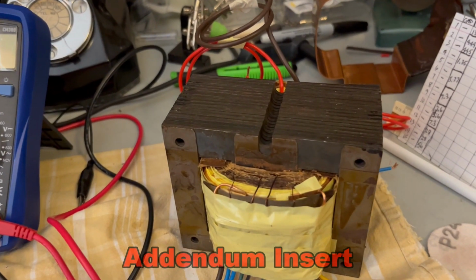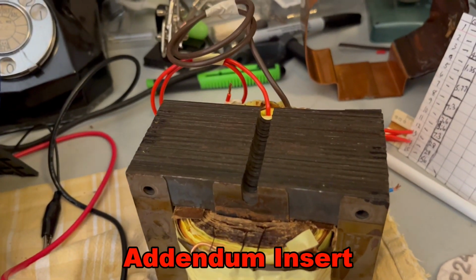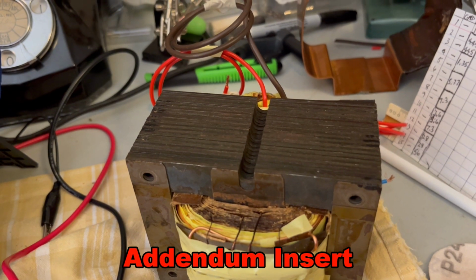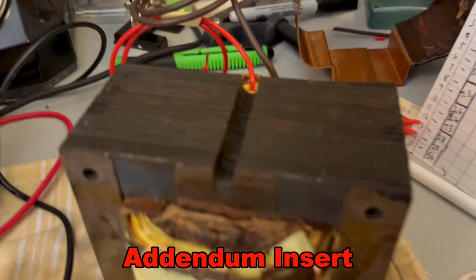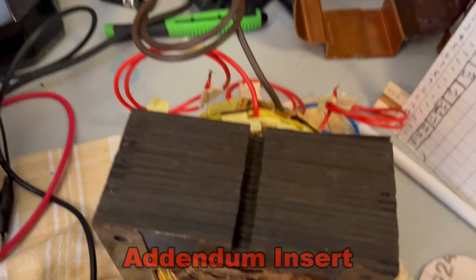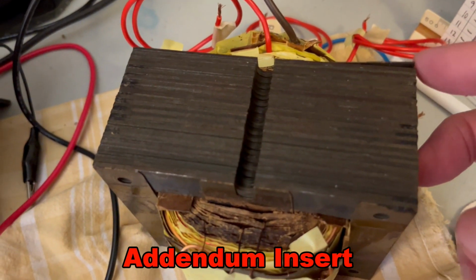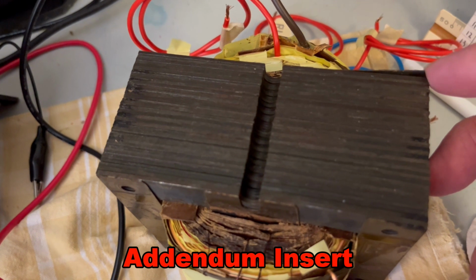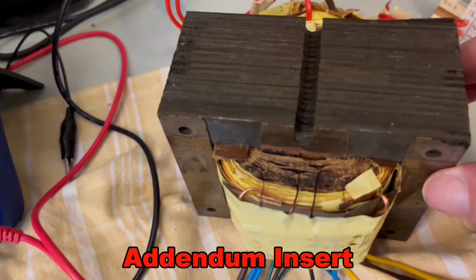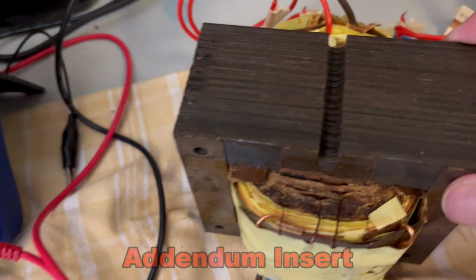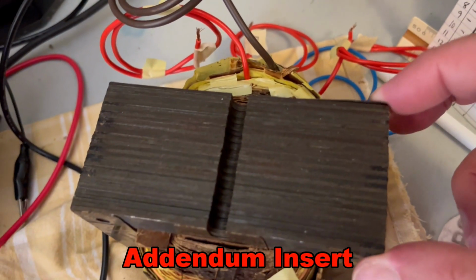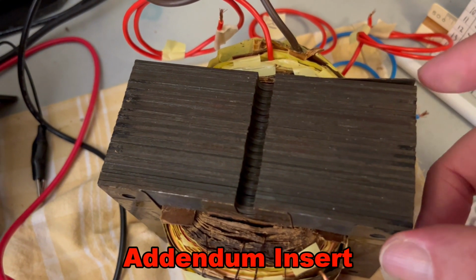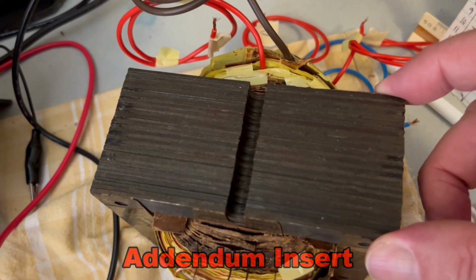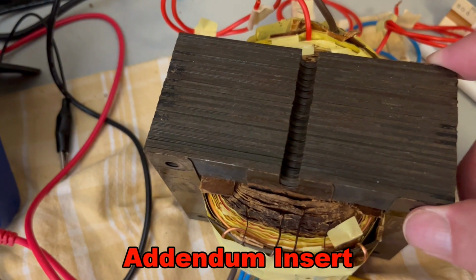I would have liked to have replaced the original paper back into the assembly, but the same can be accomplished with a thin layer of mylar. One other thing that was brought to my attention is that by this point in the rebuild, you may want to have completed all of your testing, because now would be a good time to soak the coil in an insulating varnish. The varnish seizes the coil wires in place and keeps them from rubbing against one another and causing a short.